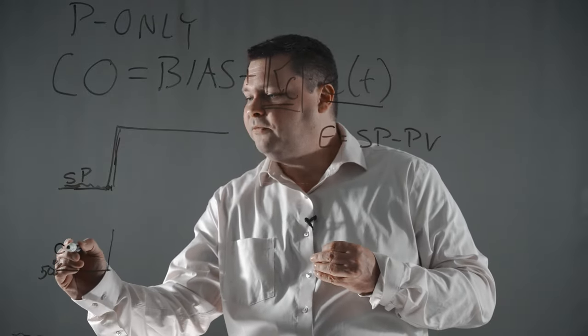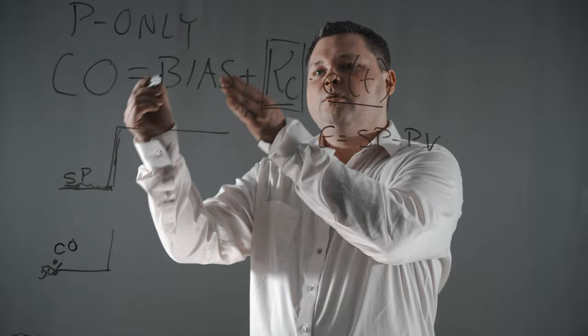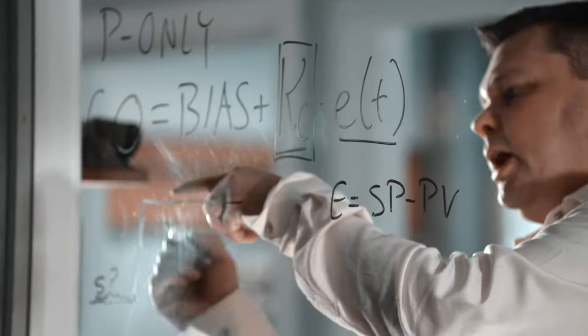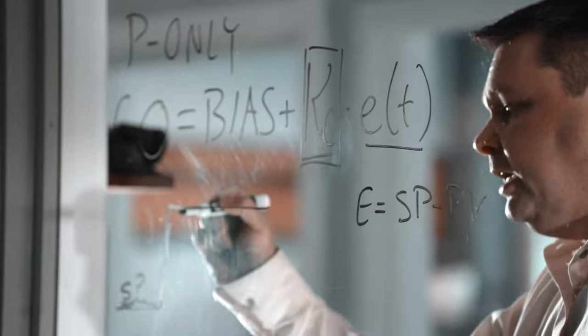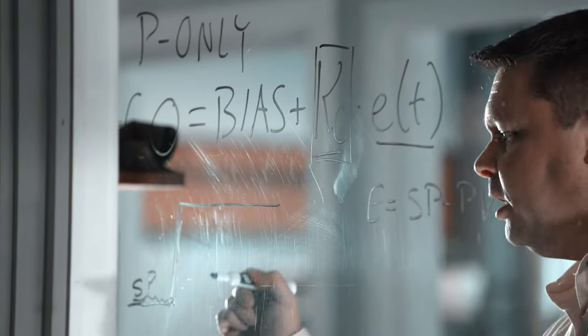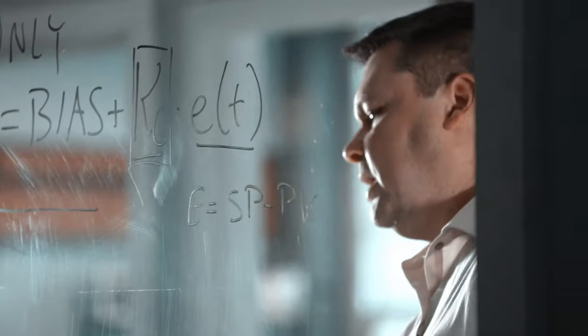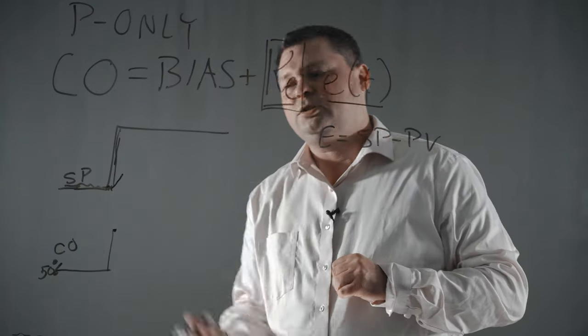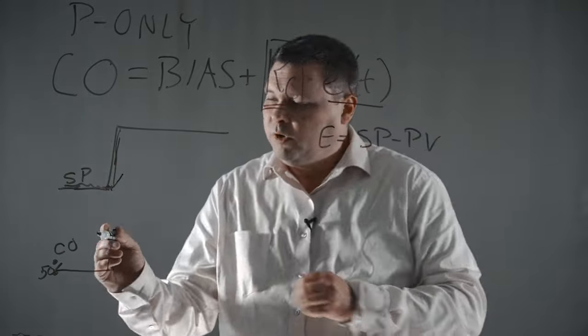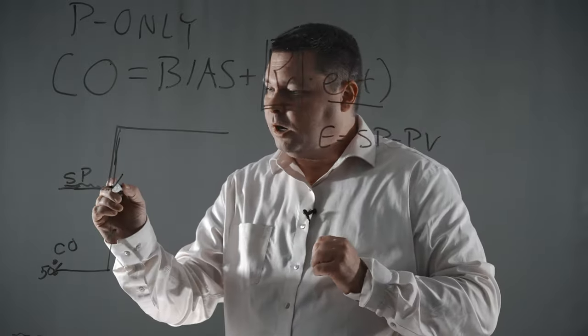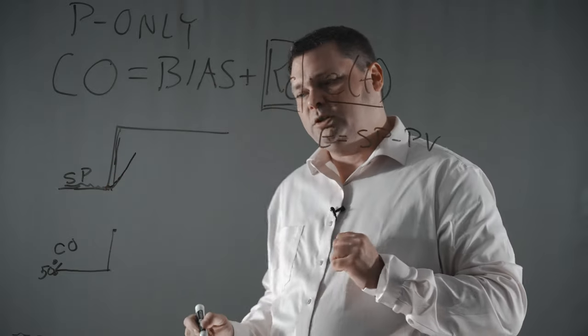If this is your controller output value, and the output is equal to the bias plus the gain times the error, when I introduced error because the setpoint changed—setpoint is up here, process variable is down there, there's some sort of error—the error times the gain is our correction. And our process variable is going to start to go up. We've opened the valve to try to bring that flow up to the target. So our process variable starts to move up.